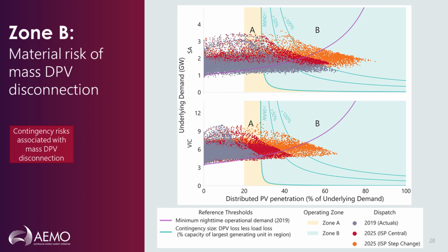So the boundary between Zone A and Zone B signifies the point where the loss of DPV generation might exceed potential load disconnection following plausible transmission disturbances. If this takes place at the same time as the loss of a large generating unit, it could potentially result in a contingency size exceeding the largest credible risk in the region. Beyond this point, additional measures will need to be in place to manage these impacts.